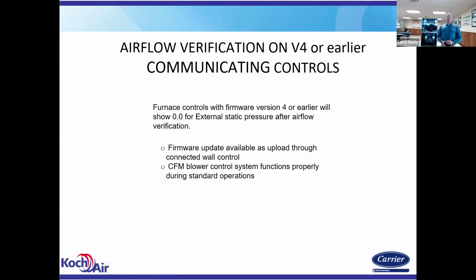We were seeing that we were getting an issue with showing a goose egg on our external pressure for our airflow verification. A firmware update was done, and on that one, it is able to be done through the communicating process. So that can be done. When you hook up, you go for software updates, it'll tell you there's a software update available for the furnace. And through the communicating, you can update the software in the furnace board. Okay.